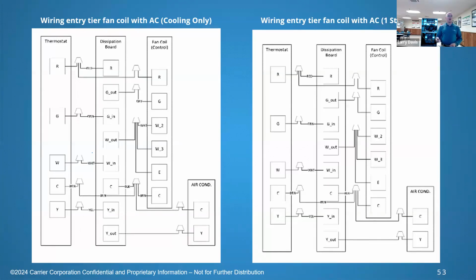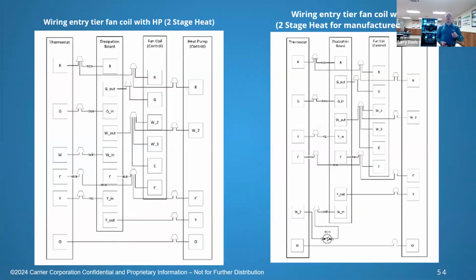Your R powers everything up. This drawing is a little bit wrong in that it's showing your dissipation board getting its R from the R terminal in the fan coil. That's not correct. It's going to come from the transformer taps, not the R terminal. That's going to be the same on all these drawings. That's incorrect.